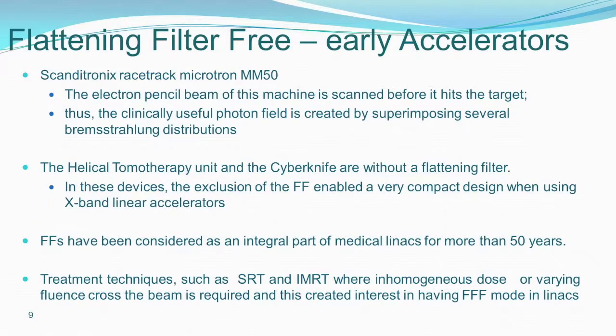Before the actual flattening filter free beam came into radiotherapy, there were other accelerators that used FFF, that is, without the flattening filter. One is the Scanditronix Racetrack Microtron, which had a scanning beam, actually composed of several Bremsstrahlung distributions, and didn't need a flattening filter. You may also know that helical tomotherapy and the CyberKnife never had a flattening filter, and not having one made it easy for them to have a compact design with the X-band linear accelerator, for both helical tomotherapy as well as for CyberKnife.